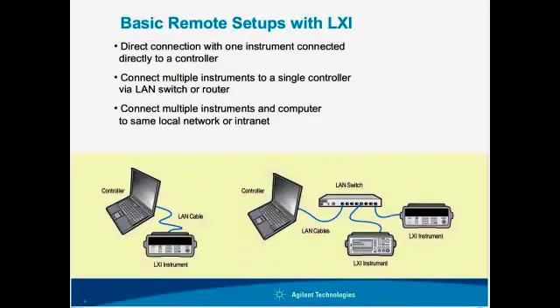So how do I control an instrument remotely with LXI? I can connect directly to it with my computer just using a LAN cable. From there, I can use drivers such as VISA, VisaCom, or IVI, and write software to control the instrument. I can use the web interface, or if you're a network programmer, you can use socket APIs to actually control the instrument.